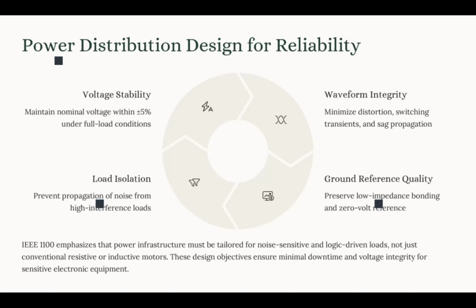Okay. Now, we should have waveform integrity, meaning we shouldn't have high distortion, switching transients, or sag propagation. We need a high quality reference ground that makes sure we have low impedance bonding in our ground system and in the connection of the power distribution to the ground system. And we have a 0-volt reference, the common mode voltage between the neutral and the ground. It's where the power distribution and ground meet each other. Okay, so we should have a 0 volt reference.